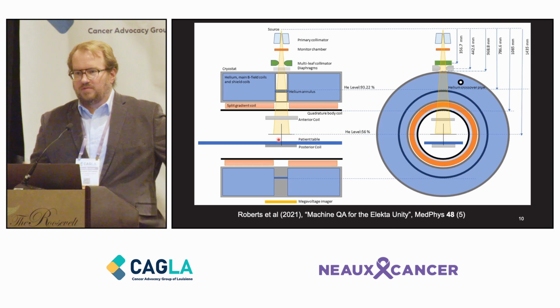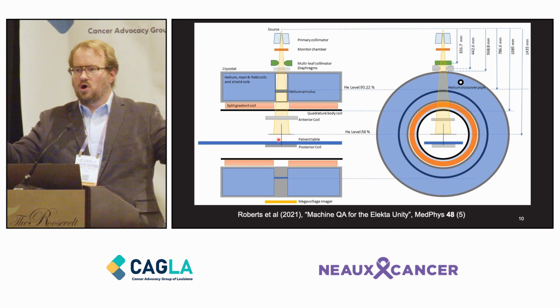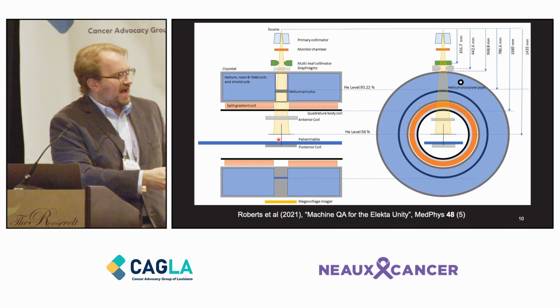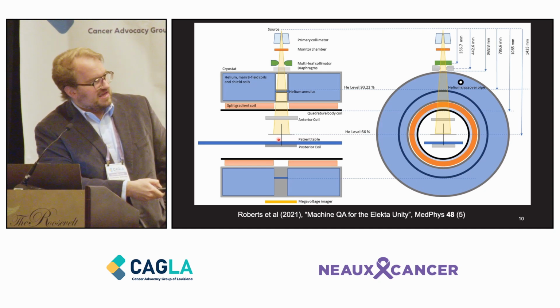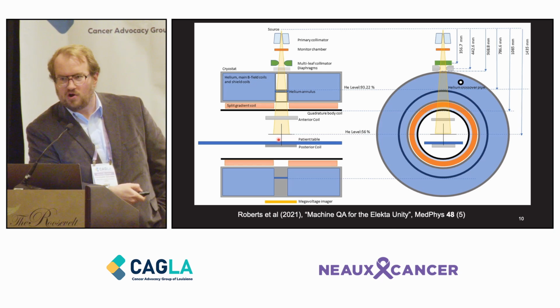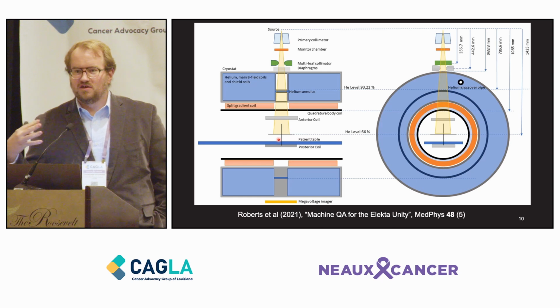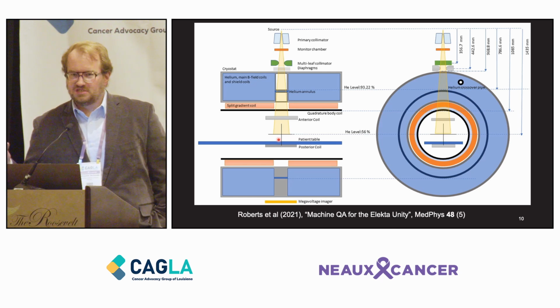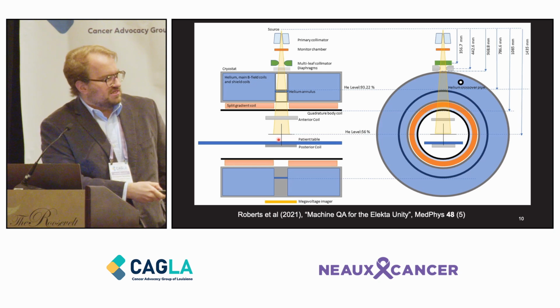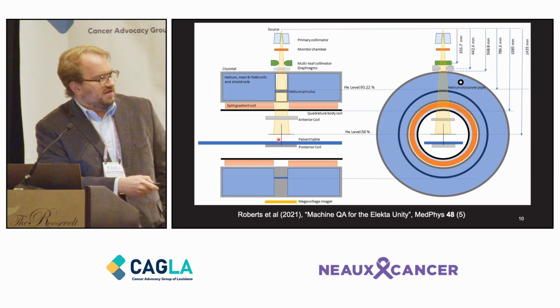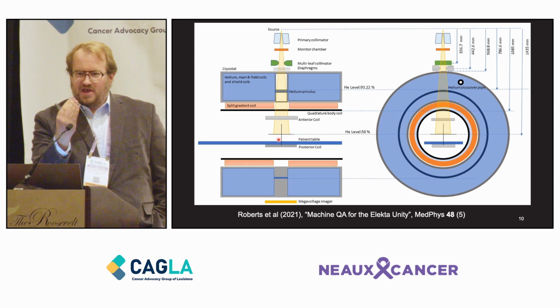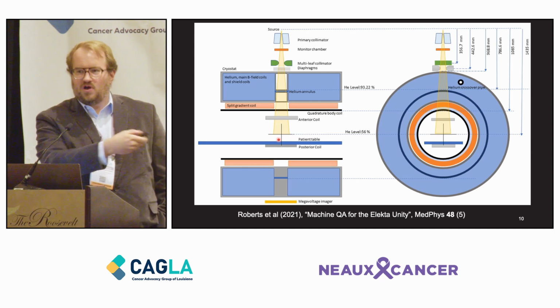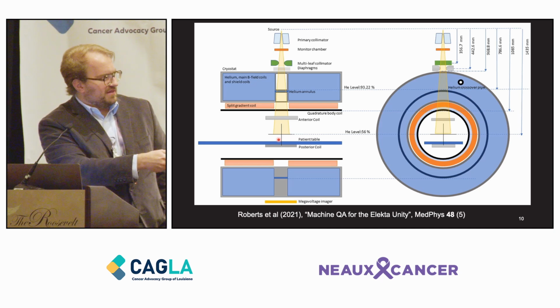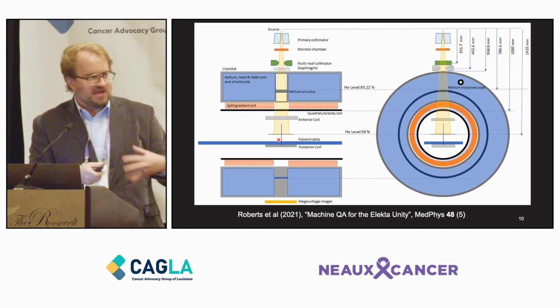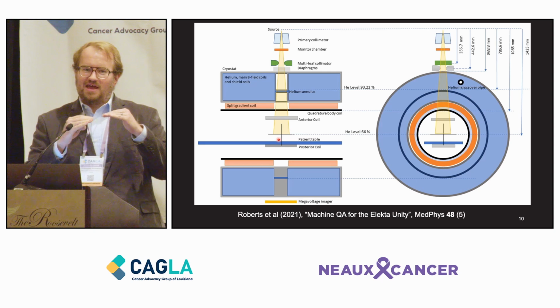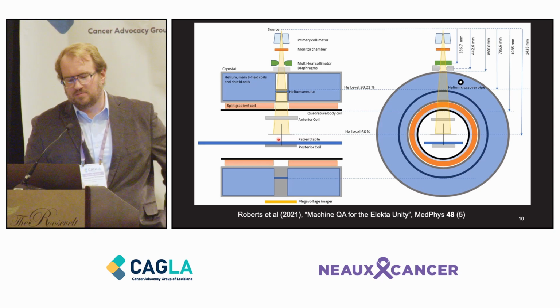The Faraday cage, which in a typical MRI vault is just built into the exterior walls of the MRI imaging vault, is there to isolate the linear accelerator from the magnetic field of the MRI and to isolate the MRI from any RF interference or noise from the linear accelerator or the motors that drive the drum. It's a custom Faraday cage built specifically for each site that isolates the LINAC from the MRI. So the cryostat and the patient are inside the Faraday cage in the imaging suite, and the LINAC is technically outside, even though it's built all around the MRI, isolated by that Faraday cage.